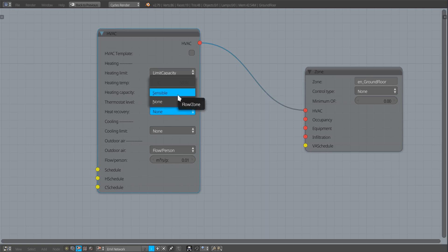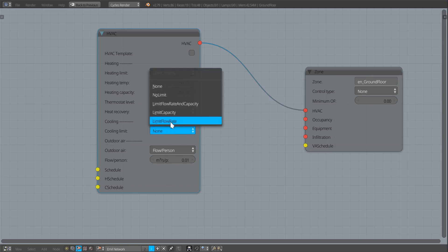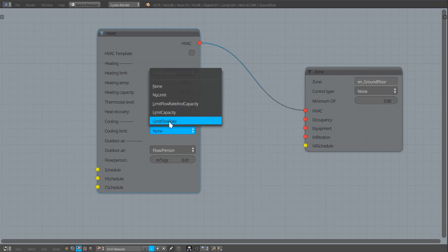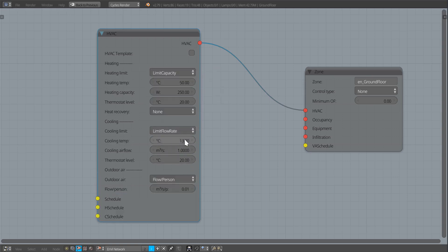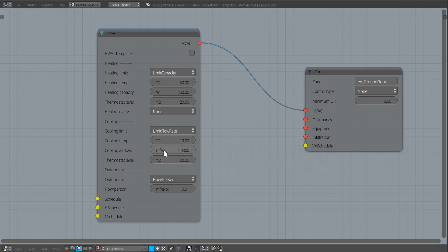We can apply a bit of heat recovery if you want to do a simple mechanical ventilation with heat recovery simulation, but I'll leave that off here. The same thing applies to cooling — it's the same nominal air-based system. For cooling we have similar options: we can limit the flow rate, control the supply temperature (default is 13°C), and control the maximum airflow rate that can come in.